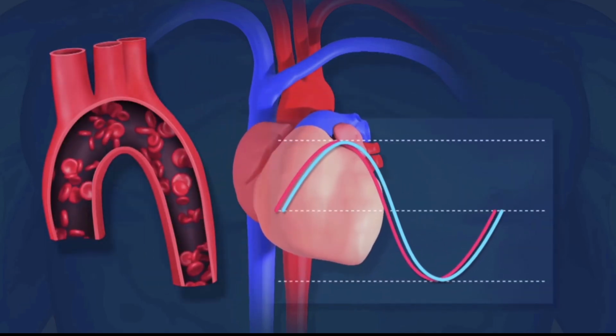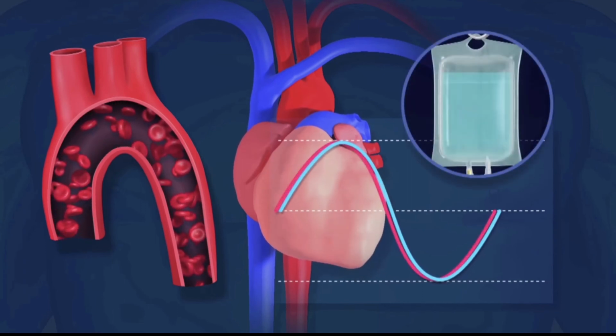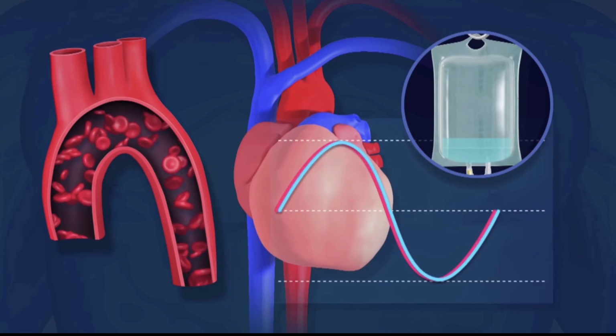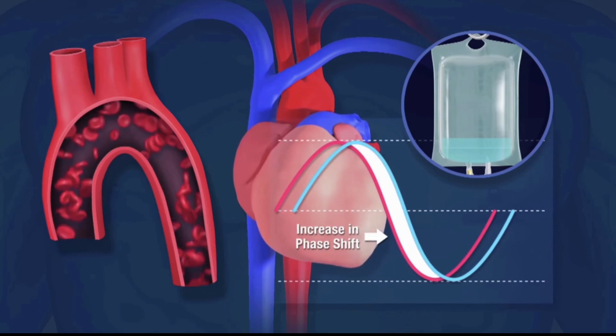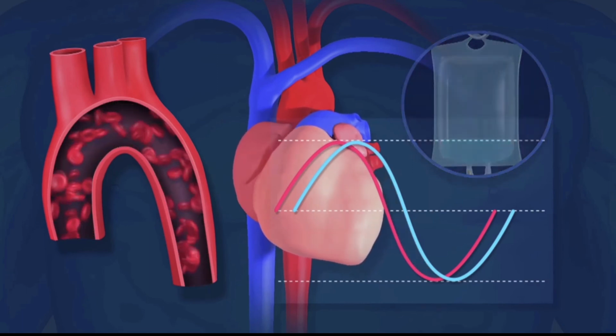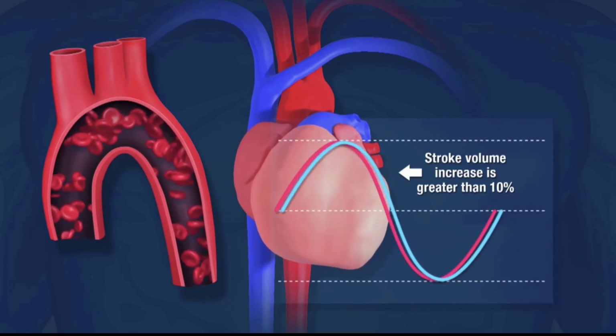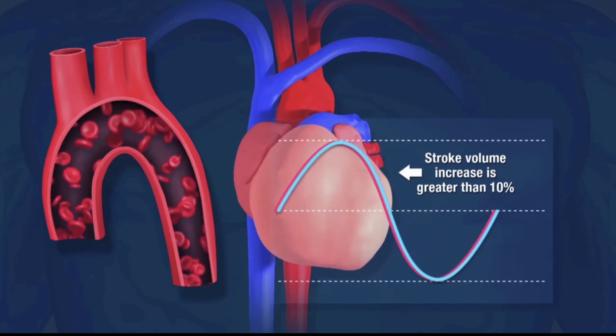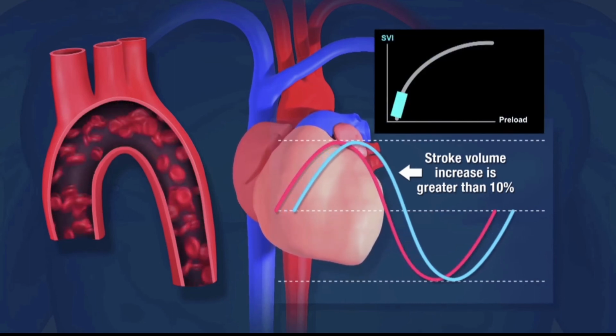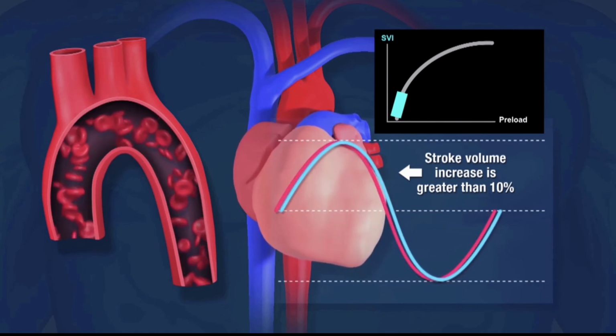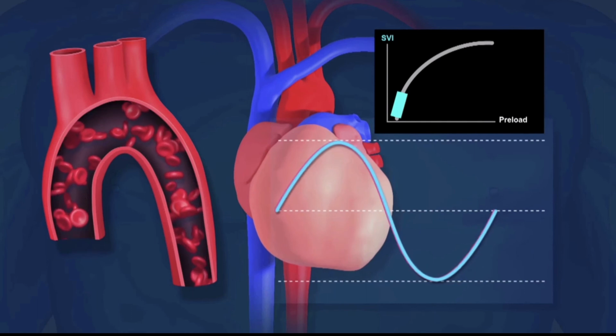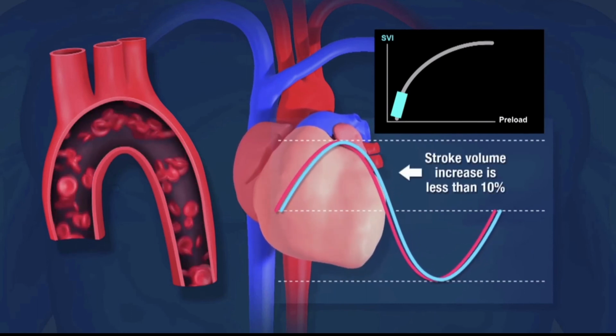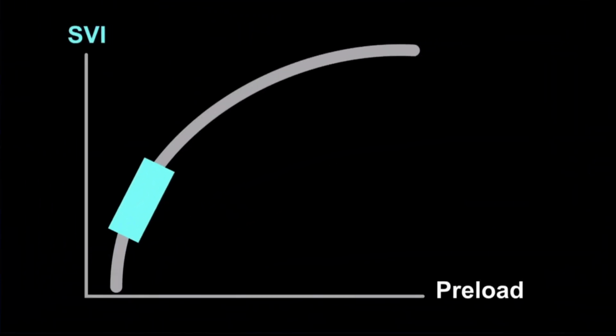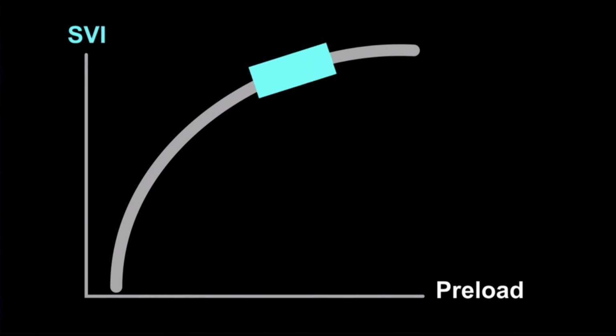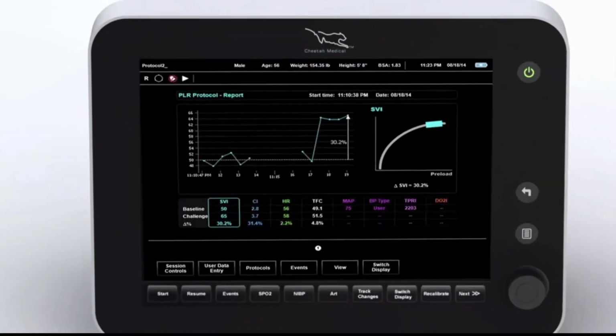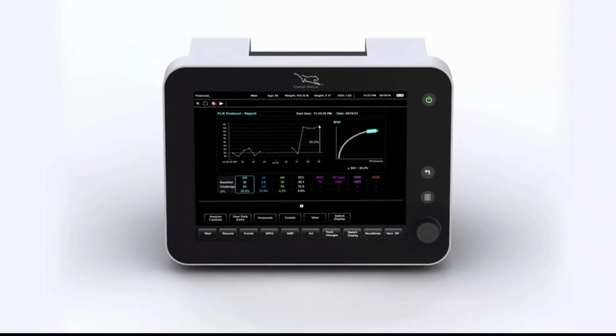To determine fluid responsiveness or volume status, a fluid bolus is delivered. If the heart can receive more fluid, we'll see greater outflow and a longer time delay, equivalent to the increase in stroke volume. If the stroke volume increase is greater than 10%, then the patient is determined to be fluid responsive. This is also represented on the Starling SV monitor by the estimated location of the indicator on the Starling curve. Its location will appear on the steep ascending portion. If it's less than 10%, the patient is considered not to be fluid responsive. The indicator will be approximately close to or on the top part of the Starling curve. Although the technology is highly sophisticated, the Starling SV is easy to use.